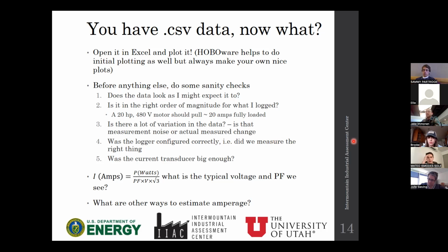Right. One thing: in that equation for the amps, usually we would be getting amps from the HOBOware, and then we could convert those amps into watts using that equation as well, right? And that equation is considering a phase 3 motor, right? It is, yeah. My point here was, before pulling up your data, to have an estimate, maybe even before you look at it, of what you think you're going to see. And if it's way different, that's maybe a red light.